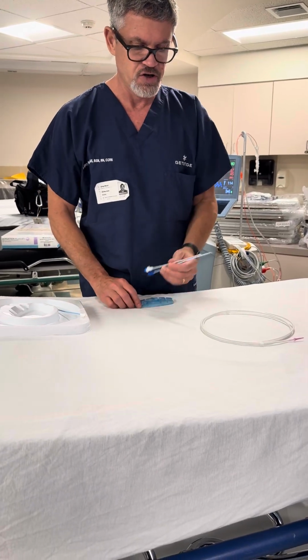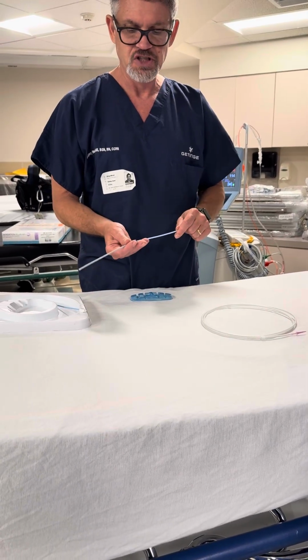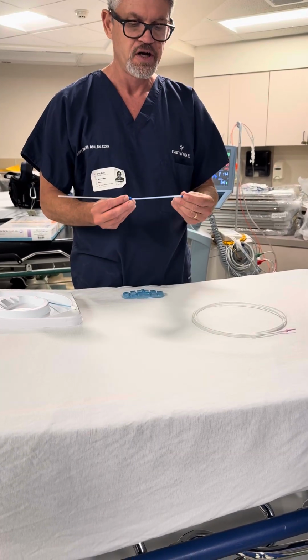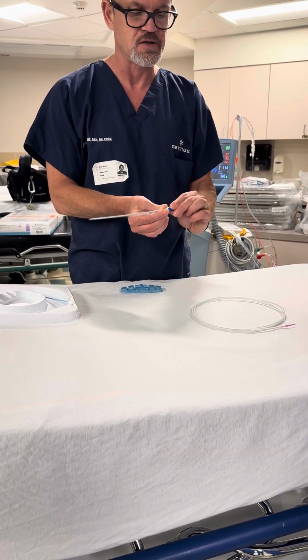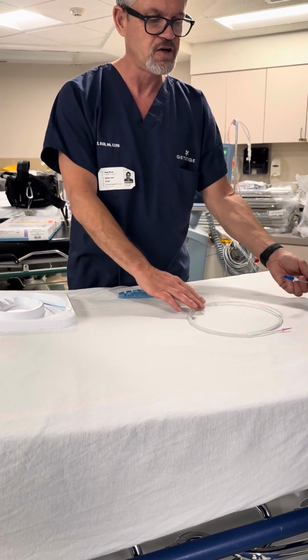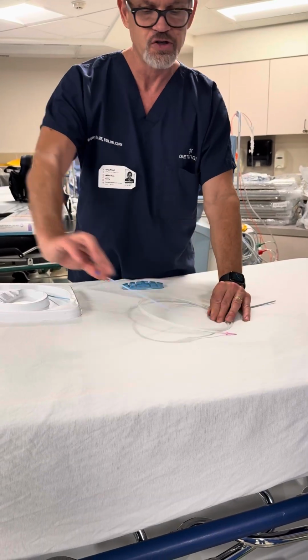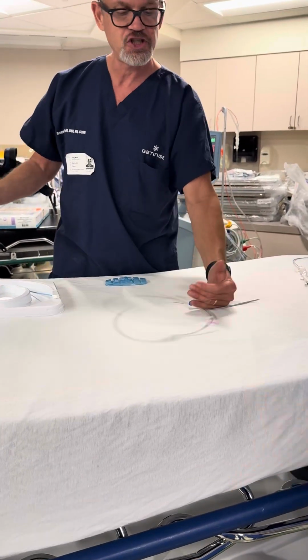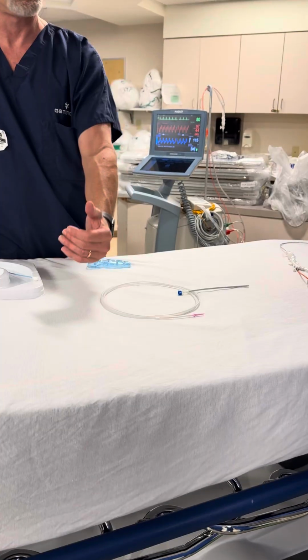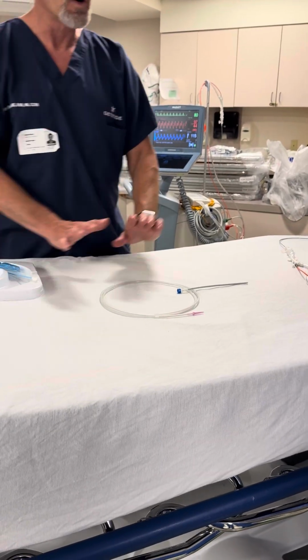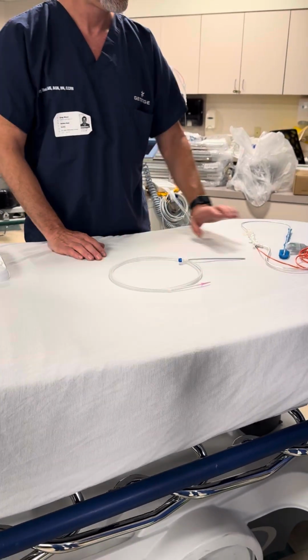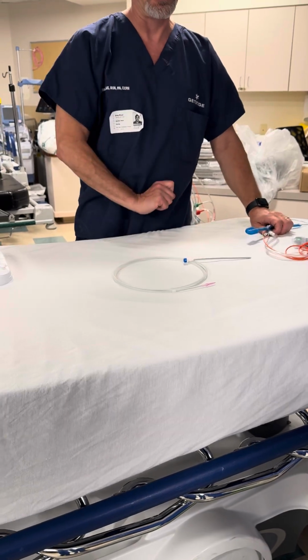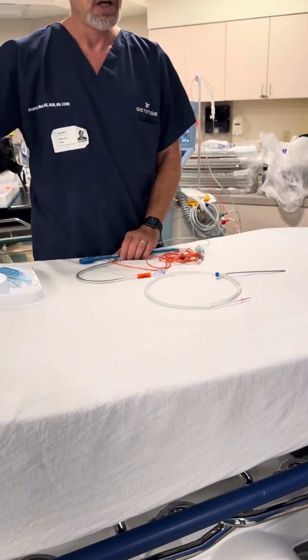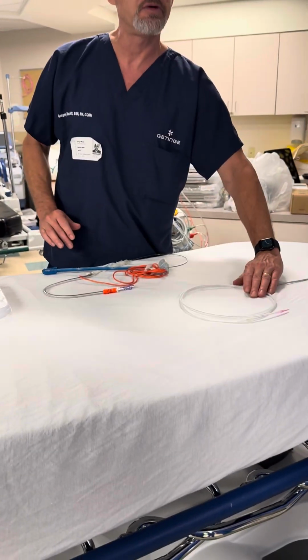And then if you're going to put the sheath in, we put the sheath and the introducer together. It's a push, turn, and lock system. And then we'll put that in over the wire and then remove our introducer off the wire. Now I have the sheath in with the guide wire hanging out. Or I just have the wire in. And the size of that sheath is 8 French. 8 French, yeah, for the 50. Right. If it were the 40 cc balloon, it'd be 7.5.